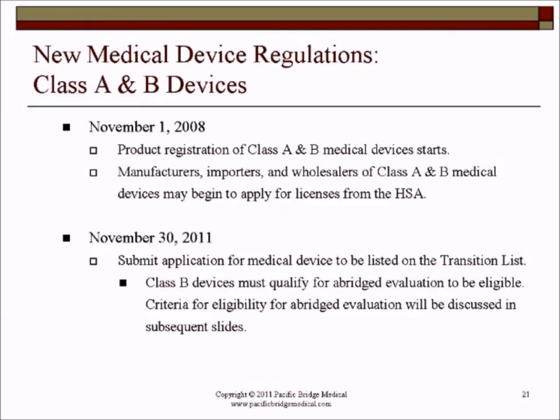What happens is, as you can see, there's this word 'transition list', and I mentioned this earlier - the main purpose of the transition list is to ensure that products that have not been registered or approved in Singapore will still be able to be supplied. I'll give you an example. If you have a product that is submitted for registration prior to this date, and come January 1st, 2012 it's not yet approved by HSA, but because you submitted prior to November 30th, HSA would put this product on the transition list, provided it is not being rejected or for other reasons. Once it's on this transition list, you can continue to supply and import this product into Singapore for sale. It will stay on this list until HSA makes a decision that the product is approved or has rejected the product.